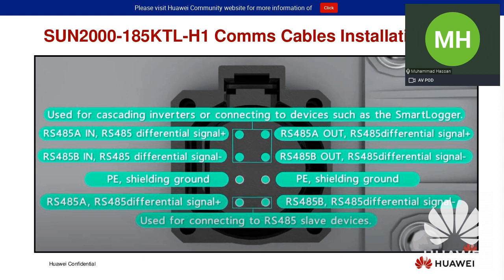This one is only applicable if you are using the RS485 communication protocol or RS485 cables to communicate with different inverters. The first two pins, the output pins, are for the RS485 A in and A out. The second pair is used for the RS485 B in and out. Pins 5 and 6 are used for the PE shielding, and the remaining pins 7 and 8 will be used for any kind of slave devices which you need to connect with the 185 KTL inverters.